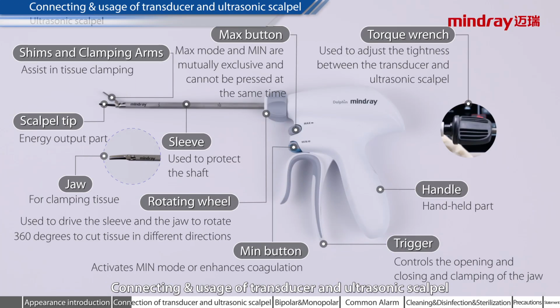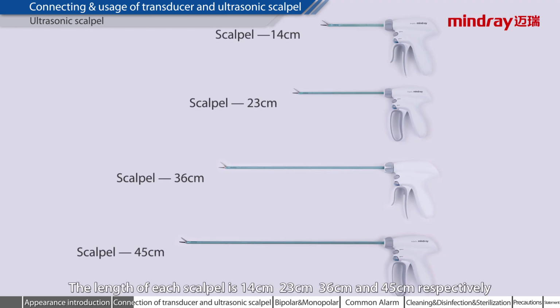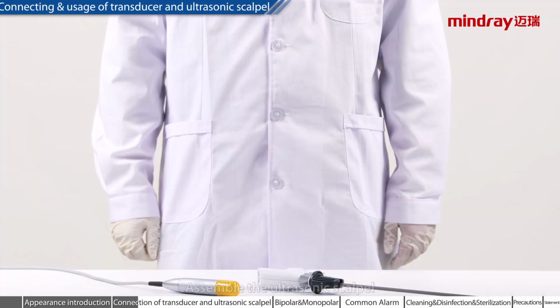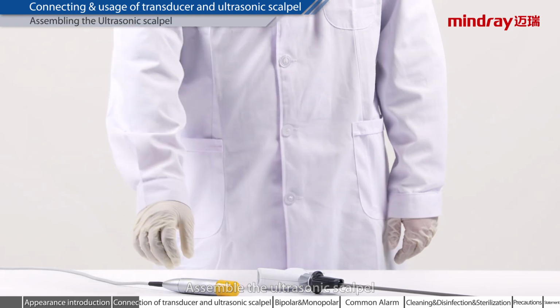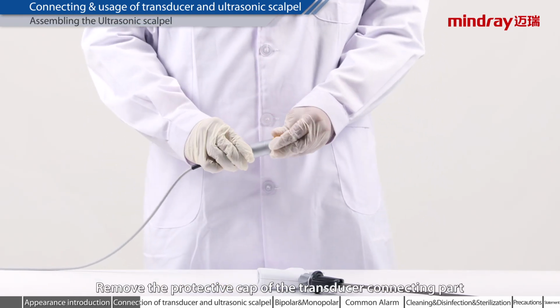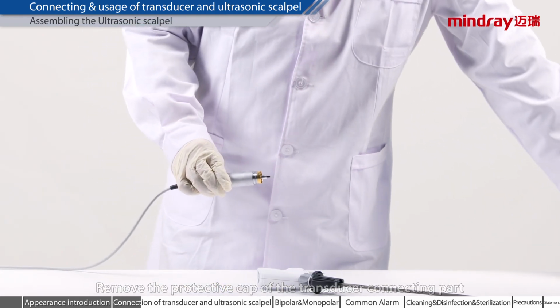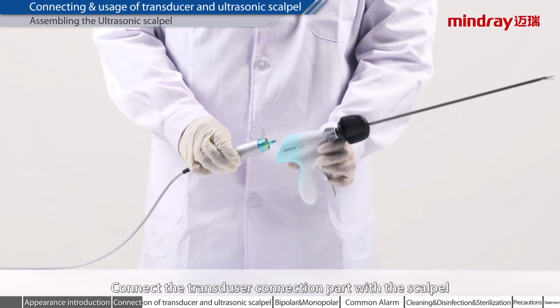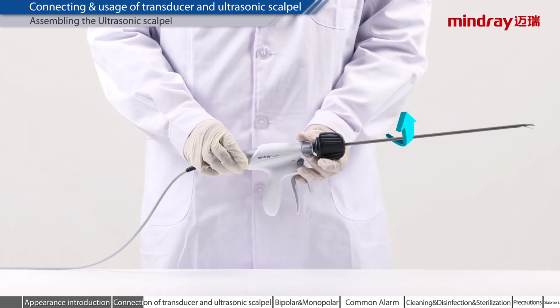Connecting and usage of the transducer and ultrasonic scalpel. The length of each scalpel is 14 centimeters, 23 centimeters, 36 centimeters, and 45 centimeters, respectively. Assembling the ultrasonic scalpel. Remove the protective cap of the transducer connecting part. Connect the transducer connection part with the scalpel.